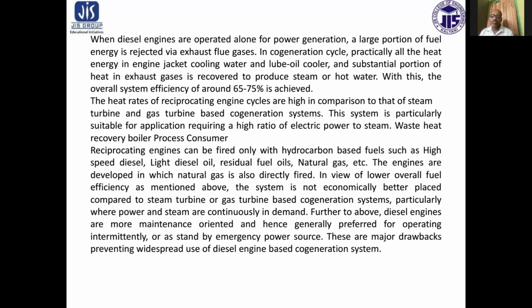The heat rates of reciprocating engine cycles are high in comparison to those of steam turbine and gas turbine based cogeneration systems. This system is particularly suitable for applications requiring a high ratio of electric power to steam. Reciprocating engines can be fired only with hydrocarbon based fuels such as high speed diesel, light diesel oil, residual fuel oil, natural gas, etc. Engines have also been developed which can fire natural gas directly.